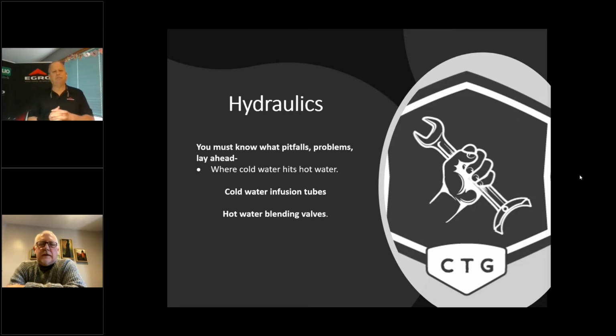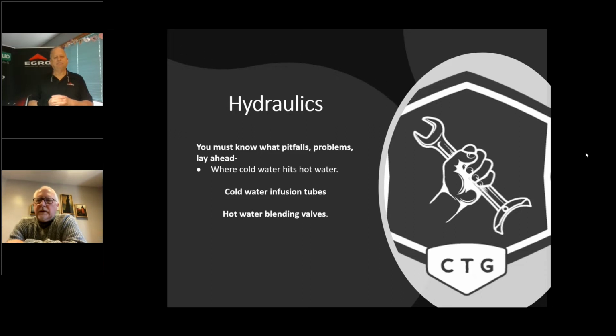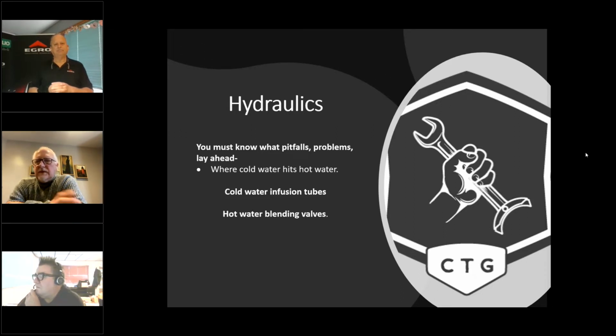Michael? Yeah, the mixing valve can also not just clog up with calcium, but it can also create a kind of corrosive effect. It can deteriorate some of the metals, especially when you're mixing steam with cold water to create hot water. At least that's what I've seen on a few occasions. So, Mike, can you go into a little bit more detail on the corrosive aspect of it?